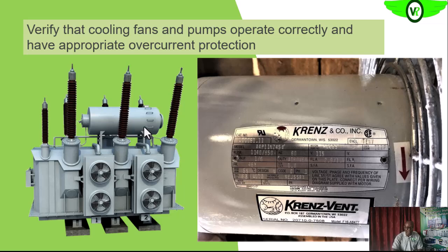So the cooling fans, as the transformer gets bigger, we need an effective cooling system. You can look at the description below for the link to our earlier training on the transformer cooling system. Okay, so for larger transformers, we actually need the fan to help force air onto the fins of the transformer to help remove heat. So this heat, as it is removed, if it is very effective, that will help to prolong the life of the transformer.